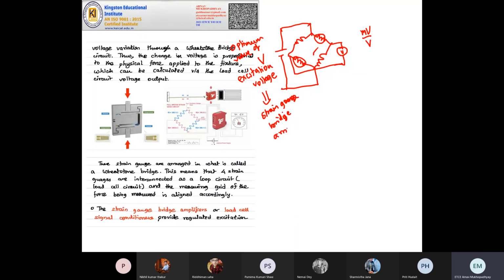Normal amplifier only amplifies the input, but the strain gauge bridge amplifier is like a feedback amplifier. It will also control this excitation voltage so that the output of the transducer lies at a proper level. But what if you change the excitation voltage? The output voltage will also change. Generally, the output of a Wheatstone bridge is in the order of millivolts. So if you increase the voltage and don't change any condition of the Wheatstone bridge, your millivolt output will also increase.